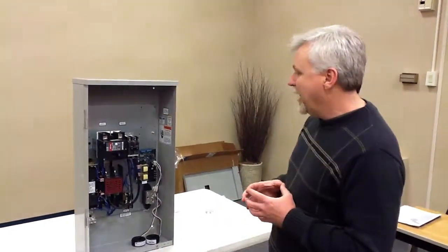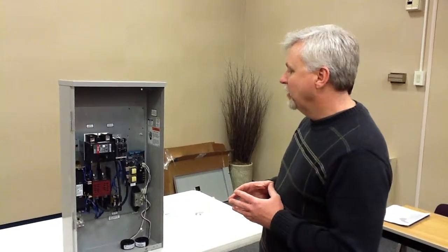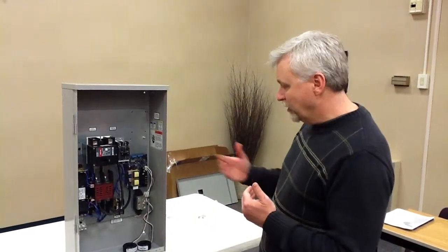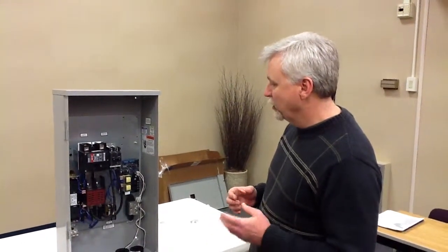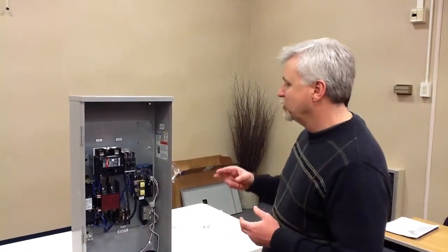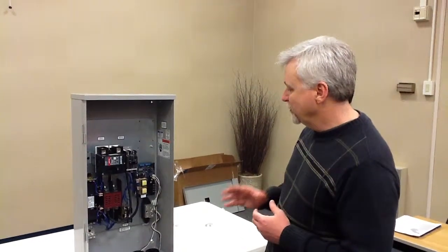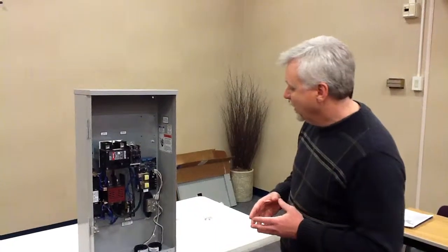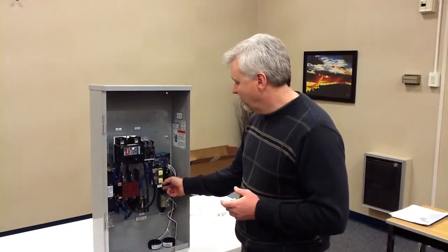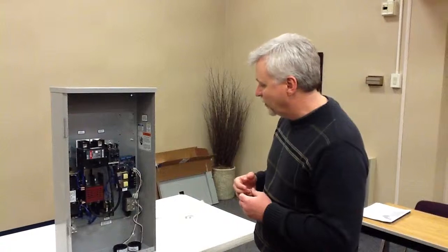And basically what happens is, during a power outage, the transfer switch will sense that the utility has lost power. It will send a signal to the generator, turn the generator on, allow the generator to reach full speed and warm up. Then it will switch over to generated power. For the first 5 minutes, anything that's on the control modules over here will be locked out. And then after a 5-minute waiting period to allow the air compressor to completely decompress, it will then see if the thermostat is telling the condensing unit to come on.